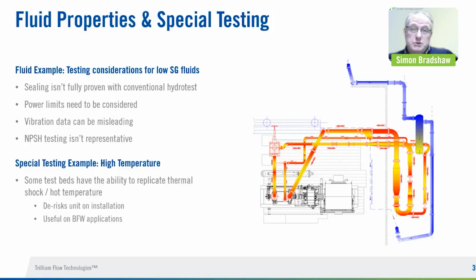Testing on water is usually more pessimistic than what you will see running with a light hydrocarbon, due to the thermodynamic effect. So again, something to consider. Although generally the water test is going to be, if it tests on water fine, it's going to be fine in the field.